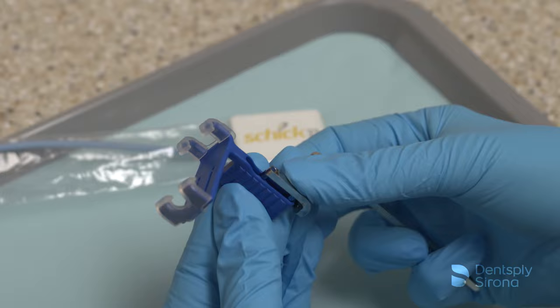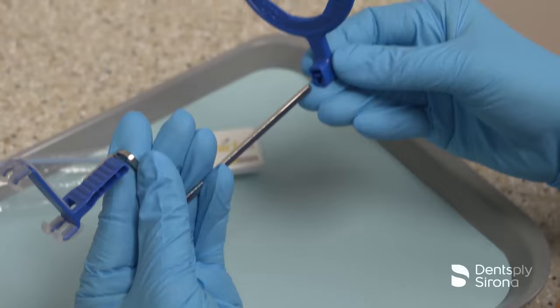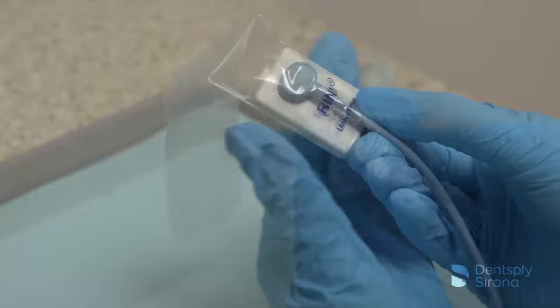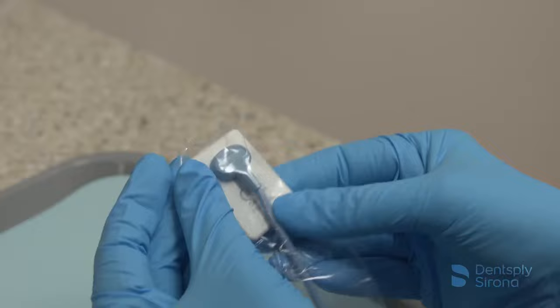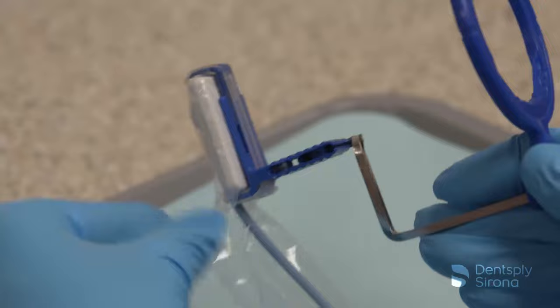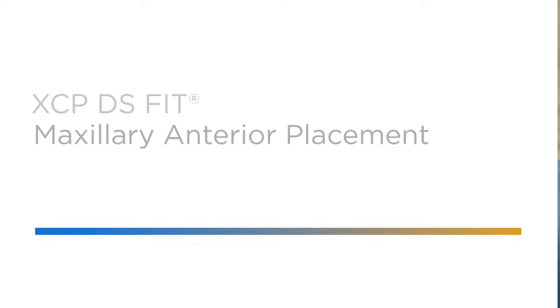To assemble the XCP-DS-FIT anterior bite block, place the blue pins on the arm into the side of the blue bite block and slide the arm into the blue aiming ring. A Rinn digital sensor cover is recommended for use with the XCP-DS-FIT universal sensor holder. After placing the sensor into a Rinn digital sensor cover, securely insert the sensor vertically into the blue bite block, making sure the active side of the sensor is against the flat surface of the bite block.